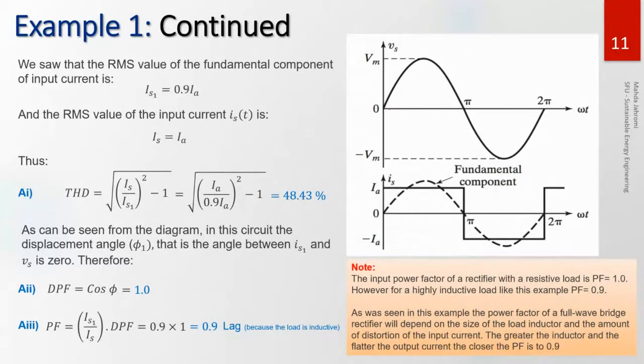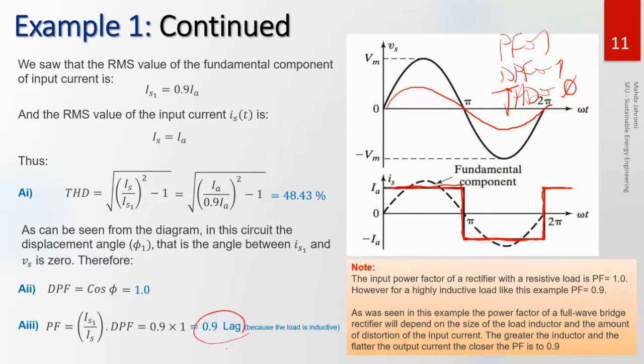Now, had we had a resistive load and the input current was sinusoidal, then the power factor would have been 1, the displacement power factor would have been 1, and the total harmonic distortion would have been 0. But because we are pulling a square wave current now, we have the power factor being 90% and the THD being 50%.